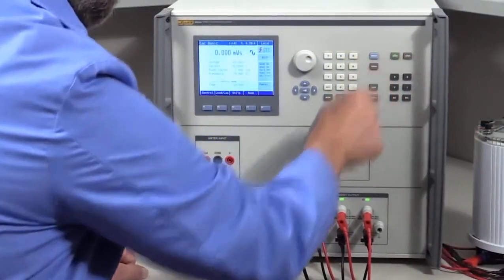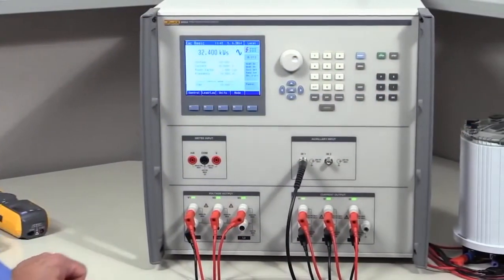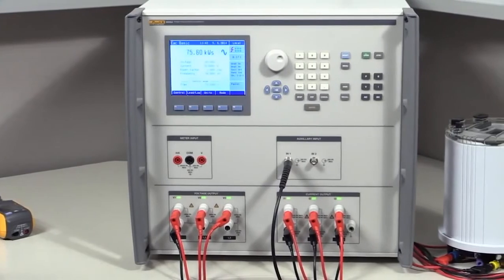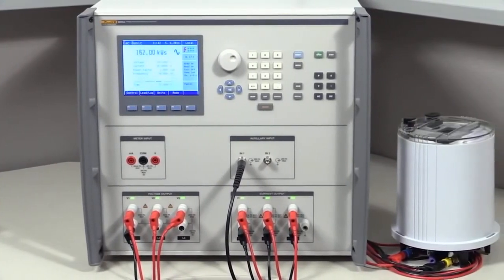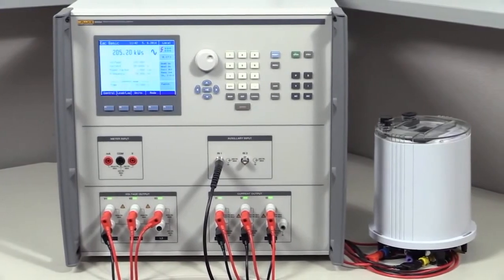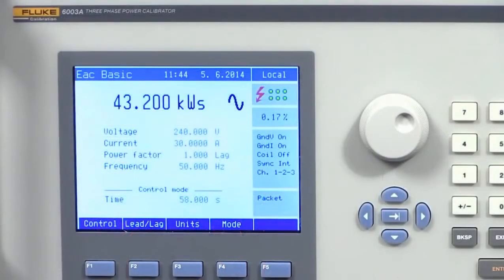You can add even more capabilities with options and accessories. The energy option adds the ability to provide calibrated power over time. This synchronized power capability is used to test energy meters. Exact amounts of energy can be delivered to the meter being tested. The 6003A's energy counter can even be used to compare the meter's energy count to that of the 6003A's calibrated source of energy.